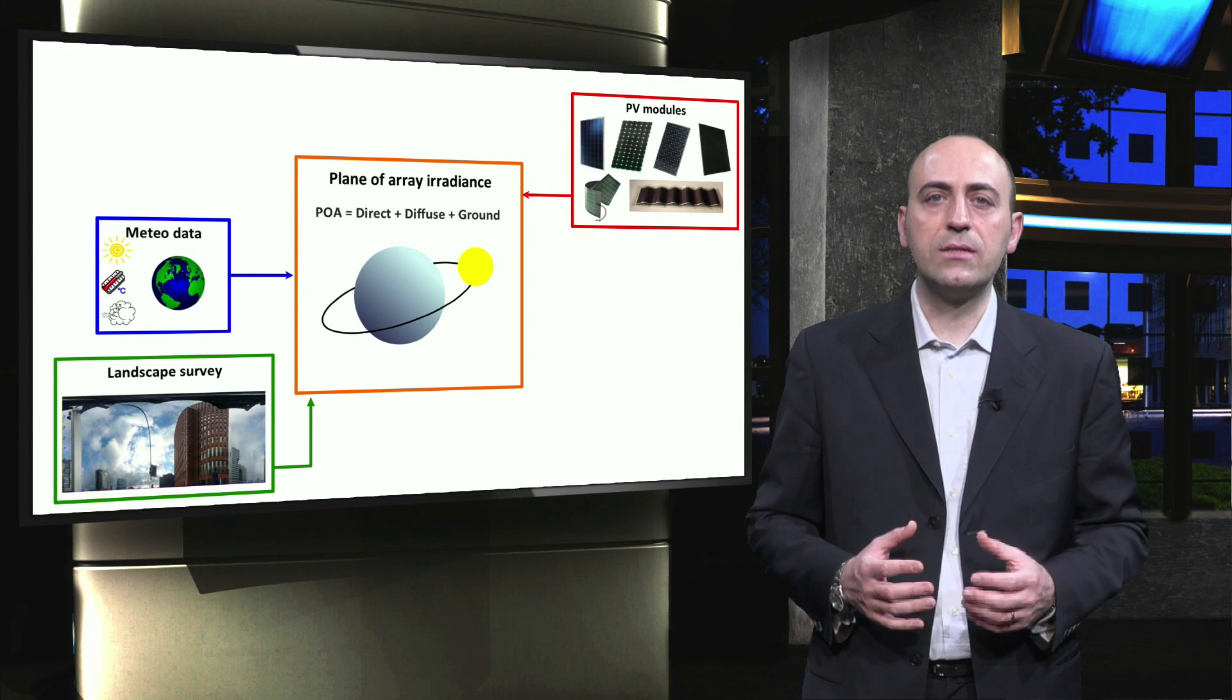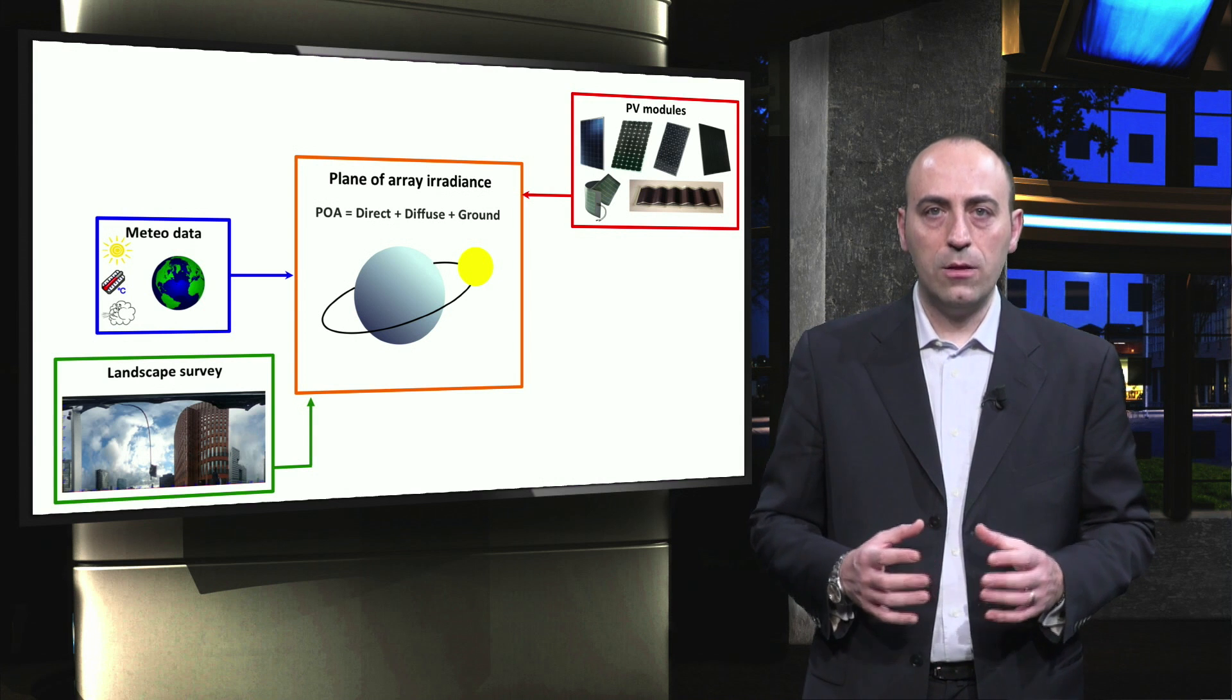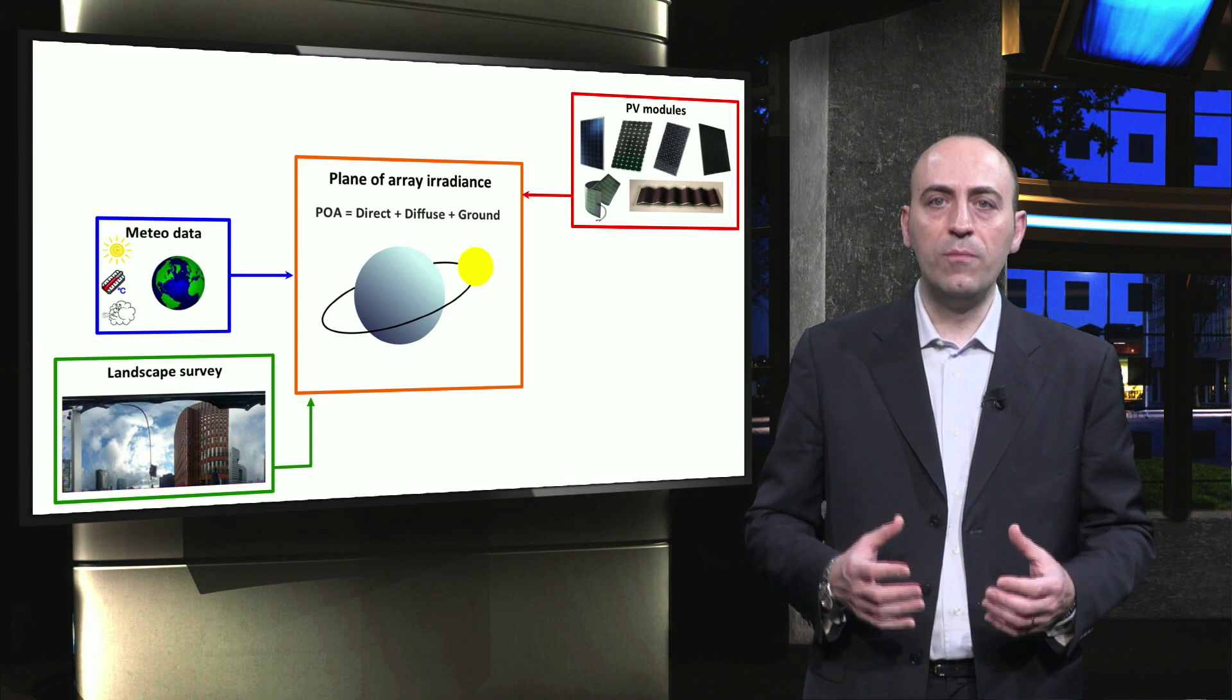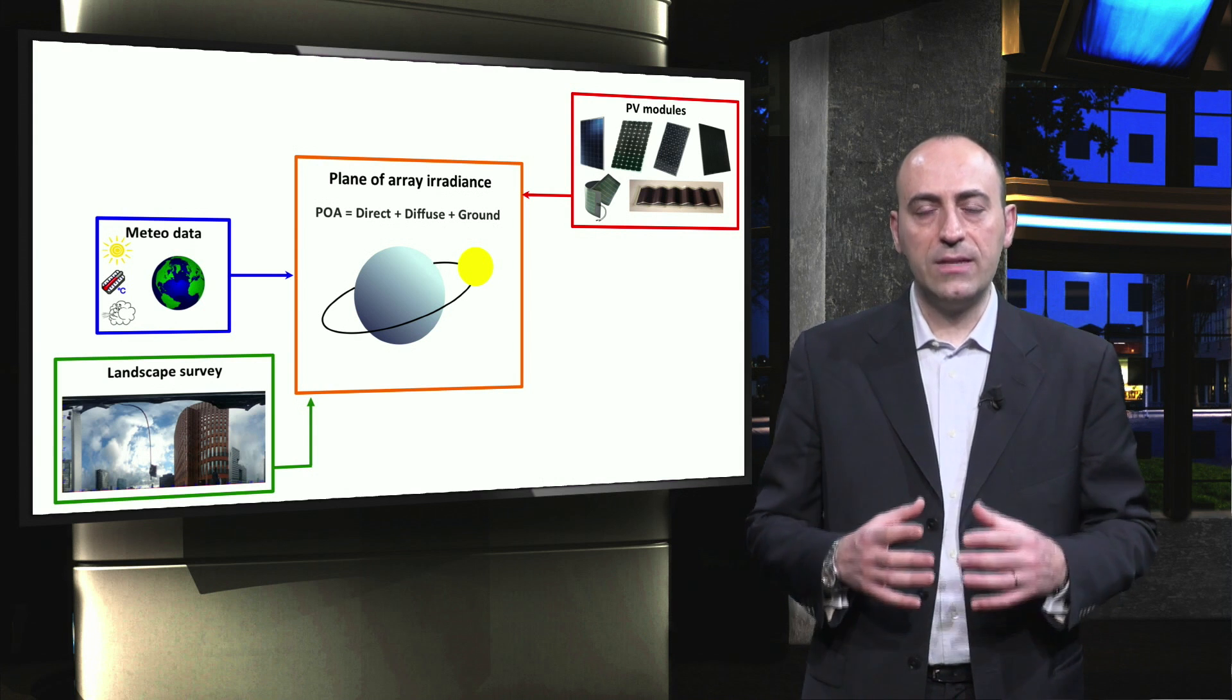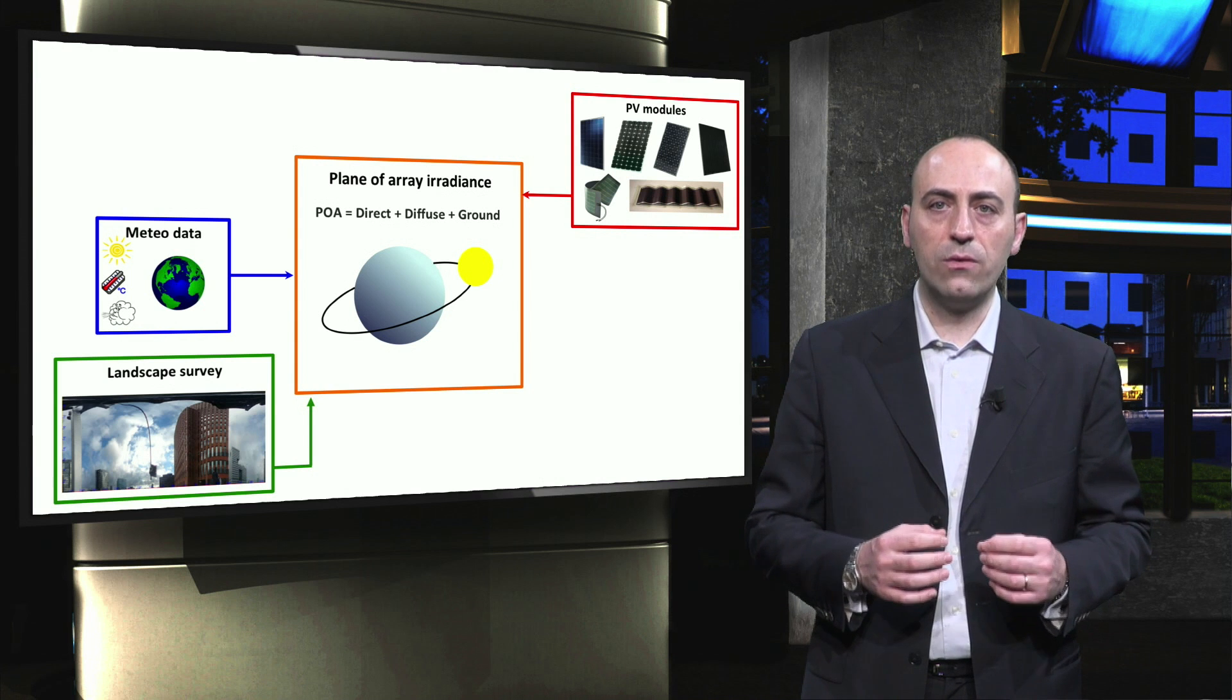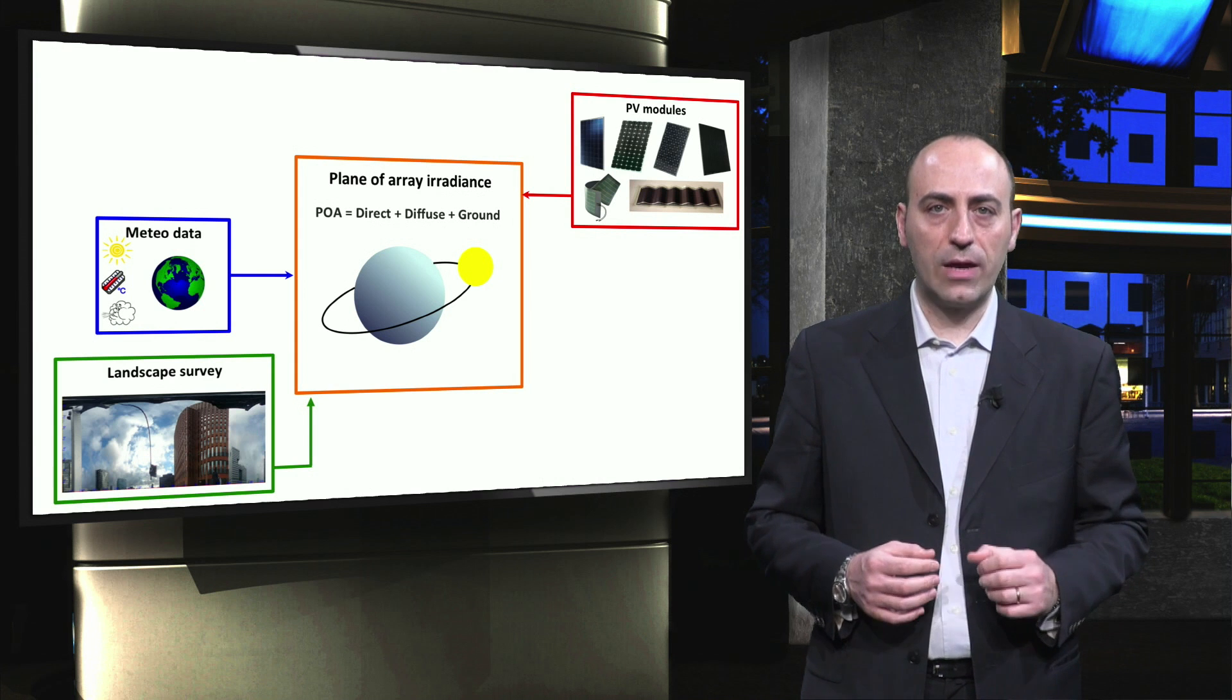The plane of array irradiance is a combination of direct, diffuse, and ground irradiance. The plane of array irradiance varies throughout the day due to the movement of the sun in the sky. By estimating the plane of array irradiance for a given module tilt, angle, and orientation, we can find the optimal tilt and orientation for a PV system in any location.